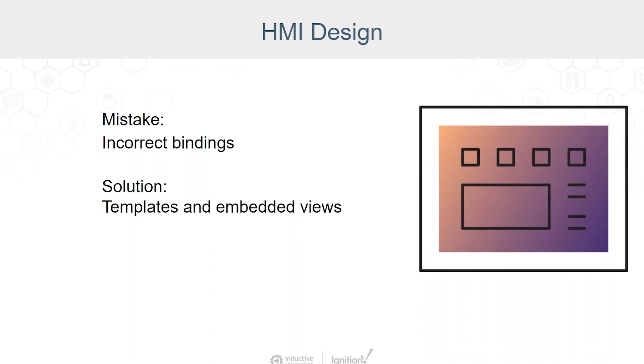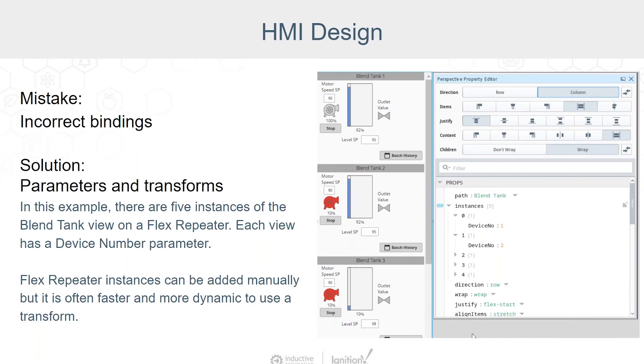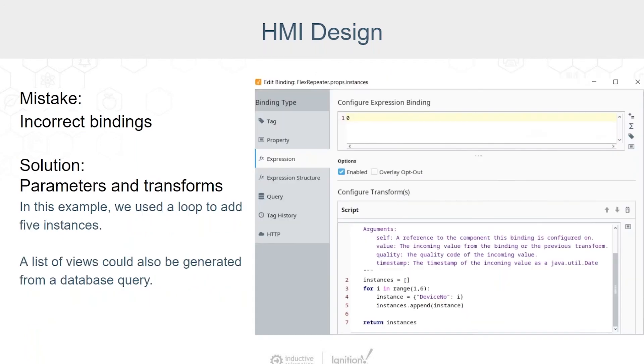If you find yourself tempted to copy and paste a group of components, consider creating a reusable view or template. One thing to avoid when embedding views is deeply nesting — stick to only a few levels. You also need to know when to use parameters and transforms instead of bindings to further increase functionality. In this example, there are five instances of the blend tank view on a flex repeater, each with a device number parameter. Using a transform linked to a source such as a query will allow your content to be dynamic. A list of views could be generated from a database query containing equipment information, so if new equipment is added, it would appear on the screen automatically.